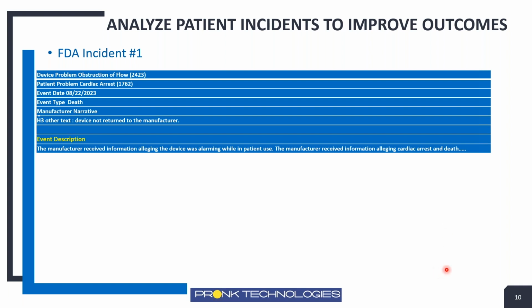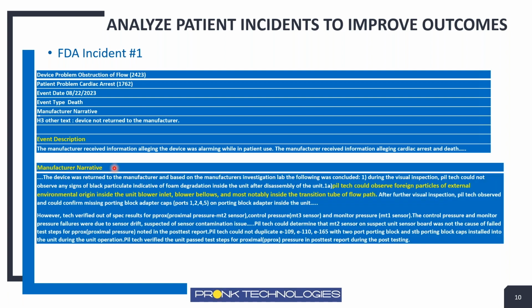Also want to cover a couple of incidents that I thought would be good to refer to as a reference as we're out there servicing ventilators. These are actual FDA reported incidents that I've summarized here. This one case here unfortunately resulted in a patient death where the clinician went into the room and the ventilator was alarming. The manufacturer's investigation, what they call the narrative here, has been summarized a little bit, highlighted in yellow. The technician could observe that they found foreign particles of external environmental origin inside of the blower inlet, the blower bellows, and inside the transition tube of the flow path. So clearly there was foreign debris coming into the unit.